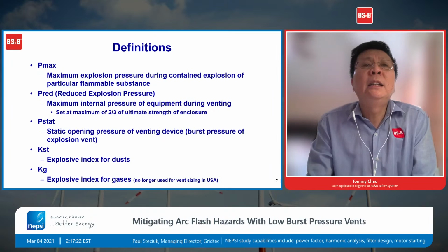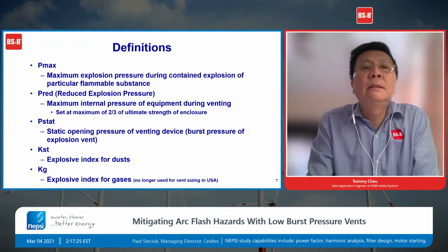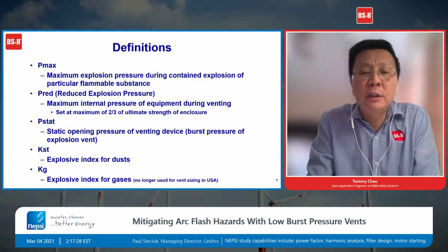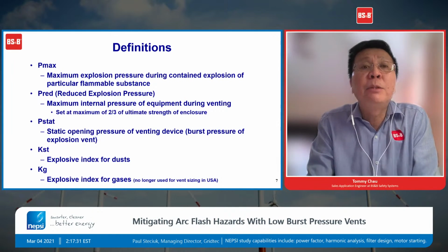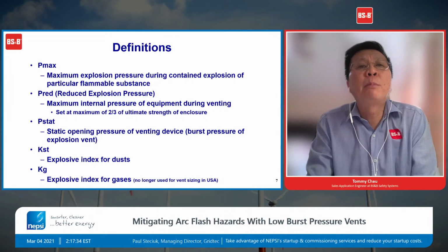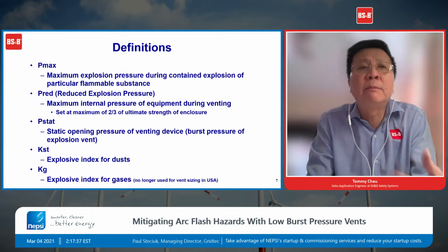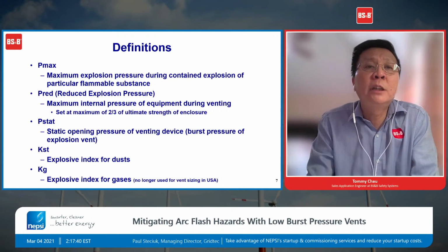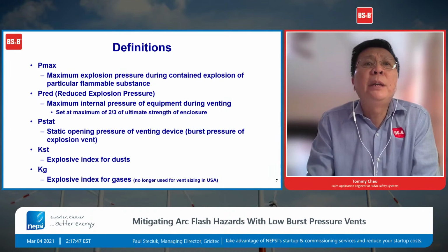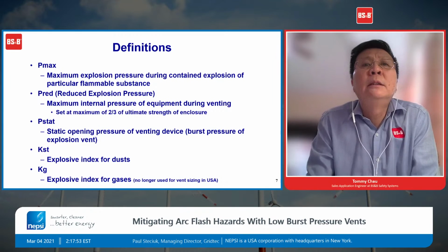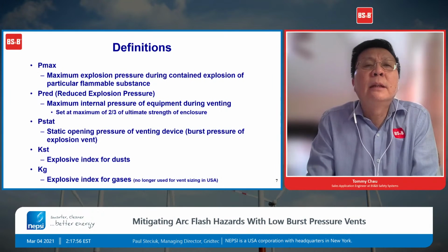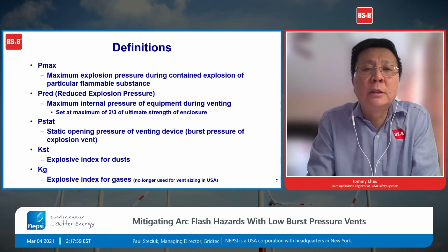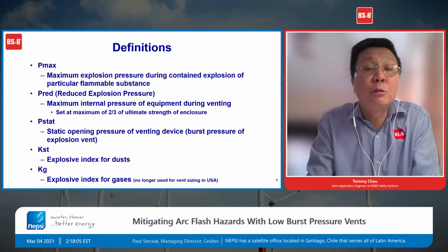Okay, here is a good definition for the different information that we normally will need to do the NFPA 68 sizing calculation. So from the bottom up is the type of dust you have or type of gas. The nominal burst pressure of the panel is the P-stat, P-S-T-A-T. The P-red is 2/3 of the maximum ultimate strength of your equipment. And the P-max is the pressure that your equipment can see if you choose not to protect it.